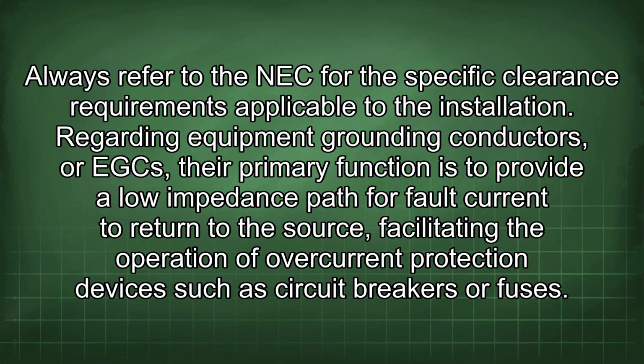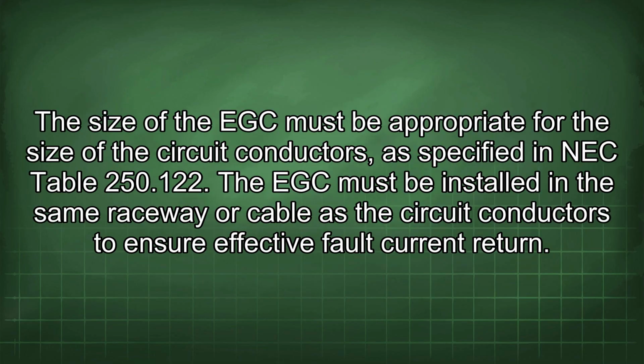Regarding equipment grounding conductors, or EGCs, their primary function is to provide a low impedance path for fault current to return to the source, facilitating the operation of overcurrent protection devices such as circuit breakers or fuses. The size of the EGC must be appropriate for the size of the circuit conductors, as specified in NEC Table 250.122. The EGC must be installed in the same raceway or cable as the circuit conductors to ensure effective fault current return.